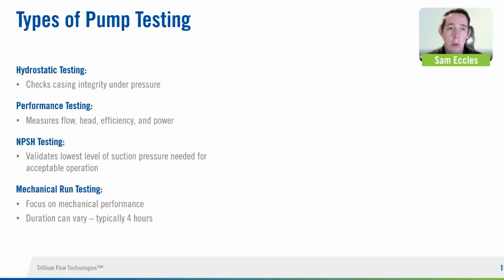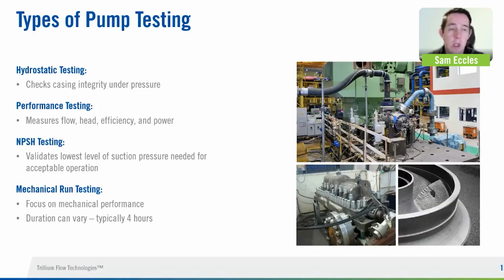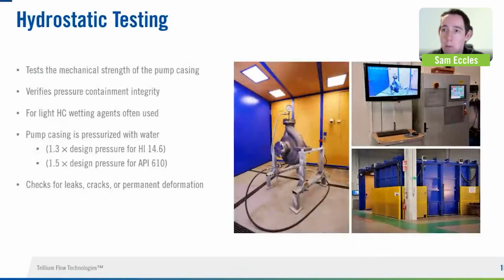So Massimiliano is going to take us through these four, but just to give a very quick overview, we have hydrostatic testing, which is the first check that's done in the manufacturing program. This is all about making sure that we'll essentially pump the case full of water, increase the pressure to about 1.5 times the load it would see in the field, and make sure the casing and bolting is performing adequately. Performance testing is, as we've just discussed, are we hitting the performance points in terms of flow, head, power, and efficiency? Following on from that, you could have NPSH testing where it's required. Typically, you'll only look at doing that testing if there is a very tight or very limited suction pressure available. And finally, mechanical run, which is basically an extended performance test that is making sure your temperatures are stable. And with that, I'll hand over to Massimiliano and let him walk through in a bit more detail.